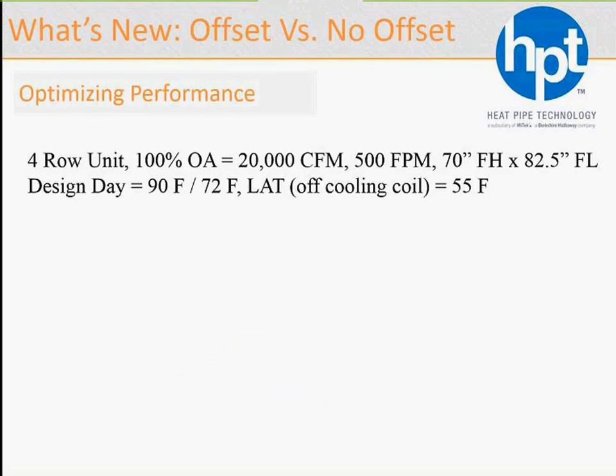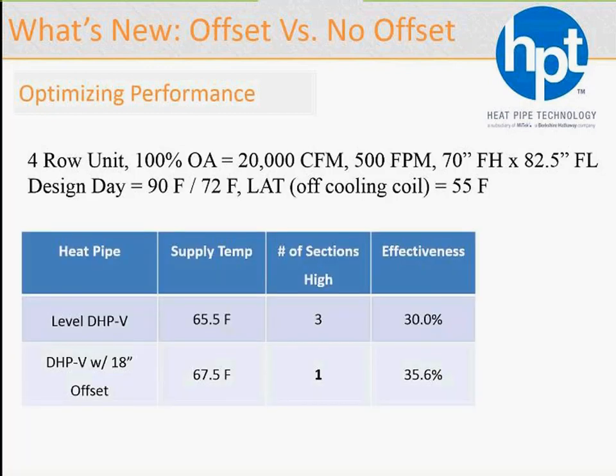Taking a look at performance comparisons, we've selected a 4-row, 100% outside air, 20,000 CFMs. Dimensions as stated here, on a design day of 90 degrees in, 55 degrees out. Let's see what we get for the offset and for the non-offset product. The level DHPV, or dehumidifier heat pipe, the V is vertical, the temperature leaving 65.5, and the number of sections are 3 because of the limitations of the height with the level. Effectiveness is 30%. It's slightly under our standard wraparound heat pipe, which we alluded to earlier.